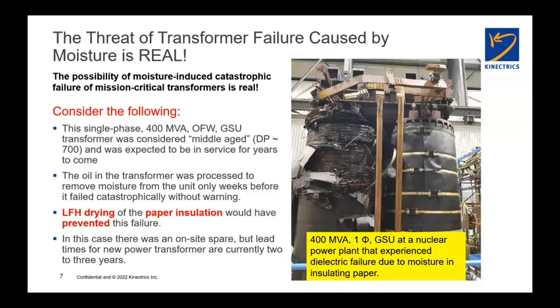And there's no doubt in my mind that had this transformer been dried with a better process, for example, low frequency drying, this failure would have been prevented. And this particular utility got really lucky. They had a spare sitting on site that they could quickly move into place. Had that not been the case, those of us in the industry are aware that at the moment lead times for new power transformers are somewhere in the 2 to 3 year range, which is almost unheard of in the industry. But that's where we are at the moment from a supply chain perspective.